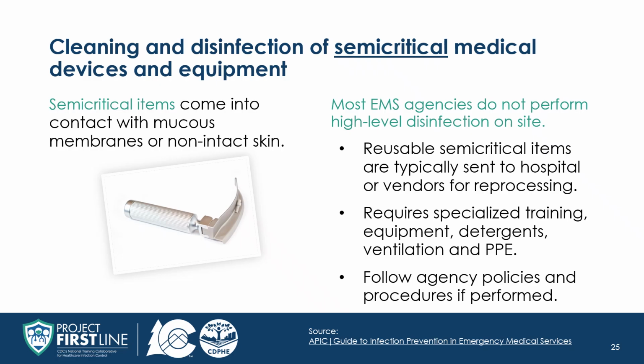Cleaning and disinfection of semi-critical medical devices and equipment. Semi-critical items come into contact with mucous membranes and non-intact skin. Semi-critical items minimally require high-level disinfection using chemical disinfectants. This level of disinfection is not typically performed on site. Instead, reusable items are often sent to a hospital or a third party as specialized training, equipment, detergents, ventilation, and PPE are required. If performed in-house, ensure that proper training has been completed and follow policies and procedures.